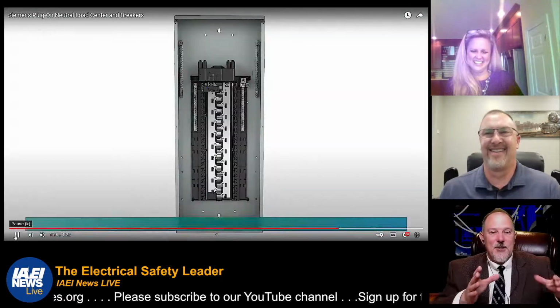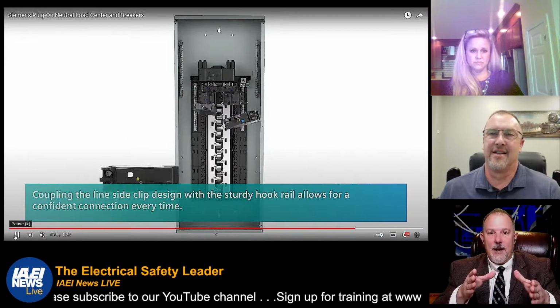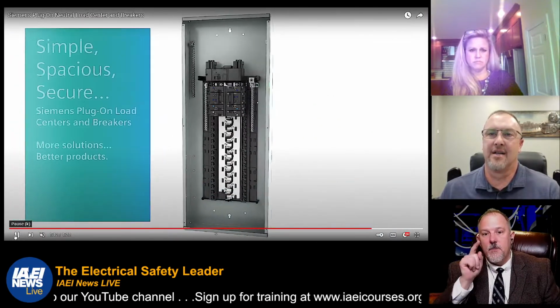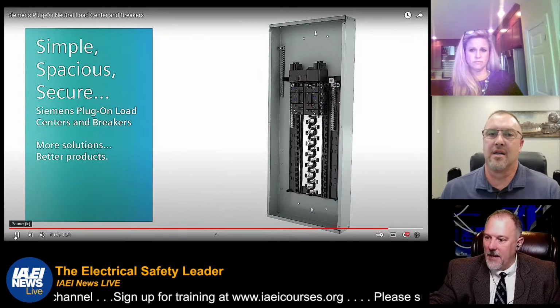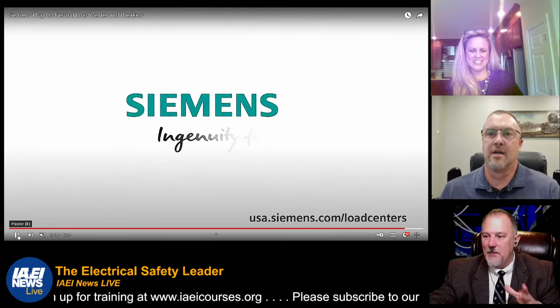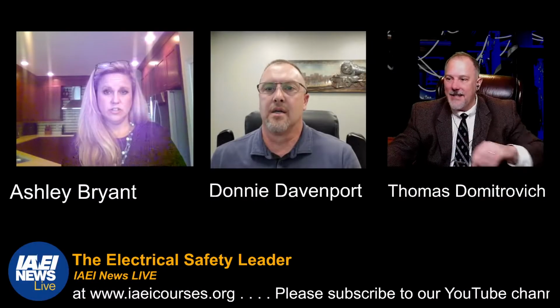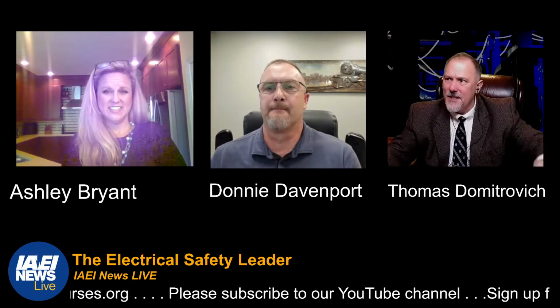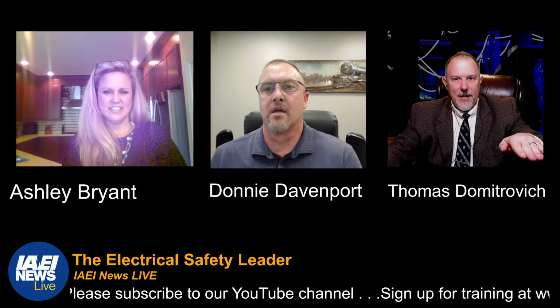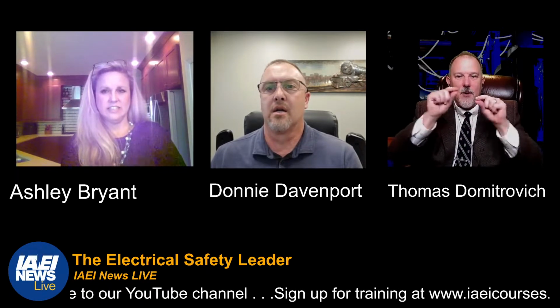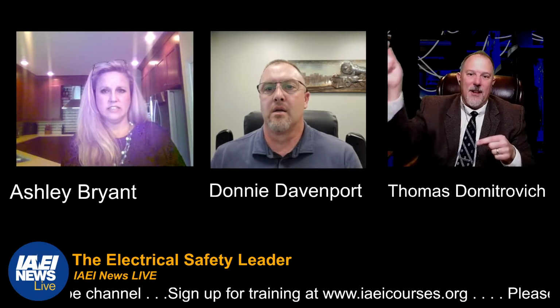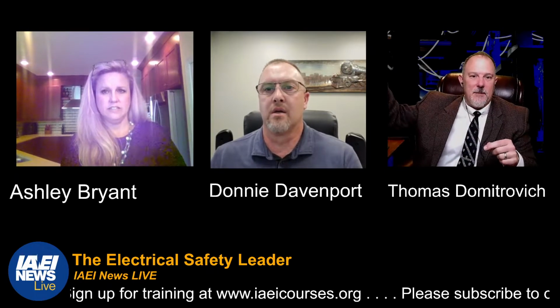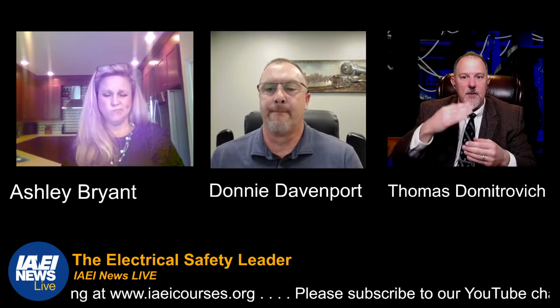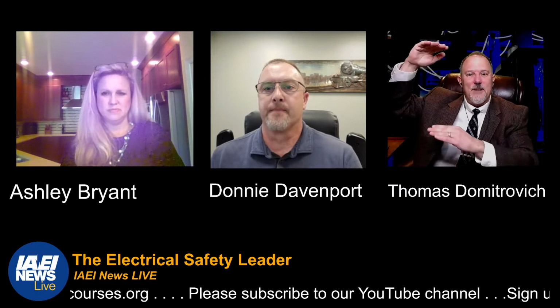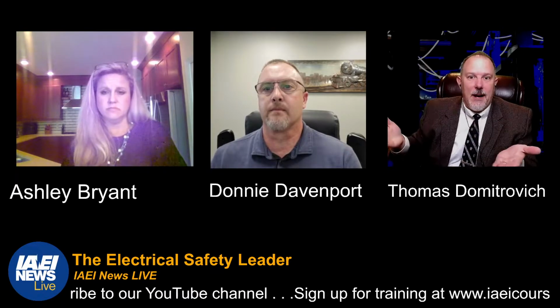So you remove that extra wire. The other thing that always bugged me about these breakers, I like when you sit down and bring a hot wire and a white wire in and land them on a lug. But with a standard thermal mag breaker, you land the hot wire, then put the neutral over on some other bus somewhere. I always want to keep them both the same length, but the neutral bars in some of these are up higher, so you can cut those neutrals shorter. But then it's hard to put wire back into a house.